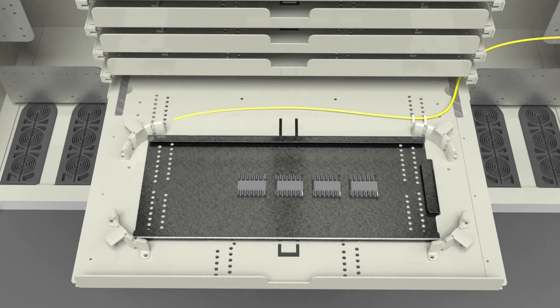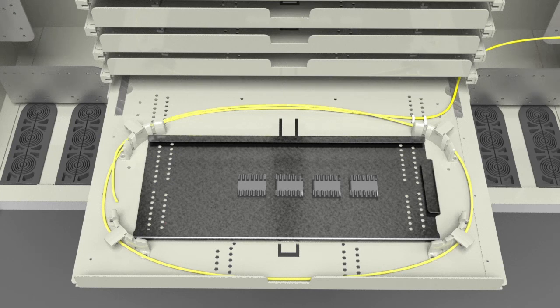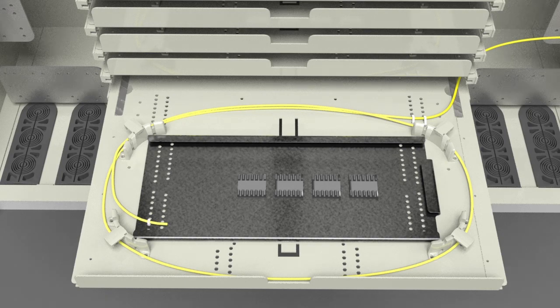Route the IFC subunit counterclockwise around the radius limiters and enter the splice tray at the left side bottom. Secure the subunit to the tray.